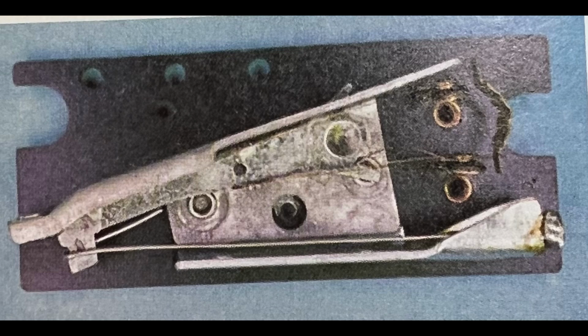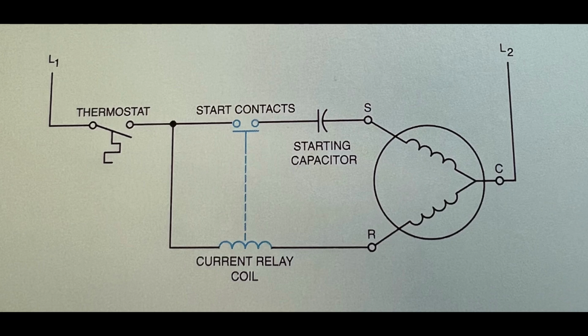Current relay. The current relay operates by sensing the amount of current flow in the circuit. This type of relay operates on the principle of a magnetic field instead of expanding metal. The current relay contains a coil with a few turns of a large wire and a set of normally open contacts. The coil of the relay is connected in series with the run winding of the motor, and the contacts are connected in series with the starter winding.